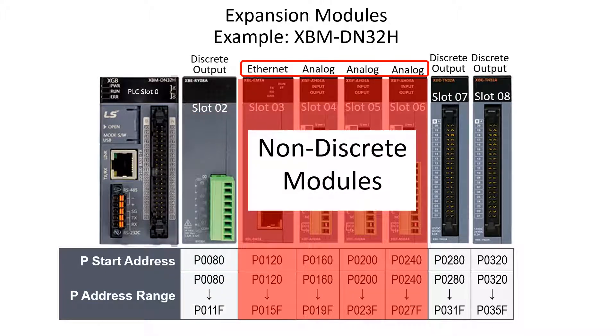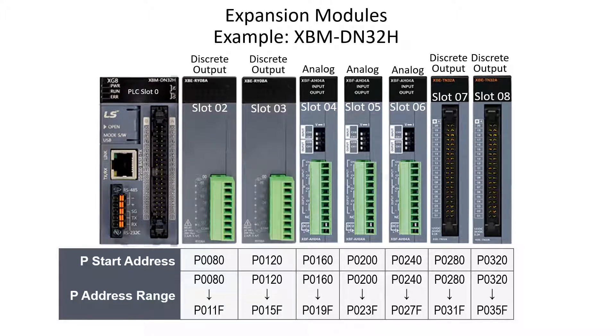Slots 3, 4, 5, and 6 are communication and analog modules. Although non-discrete modules, they are each allocated 64 bits of P data in the configuration. If the Ethernet module is replaced with a discrete output module, the P address range remains the same. The first discrete output in slot 3 will begin with the starting address of P12 bit 0.